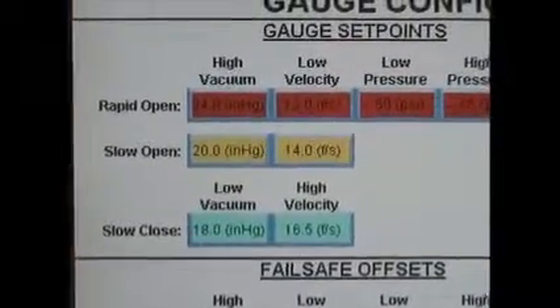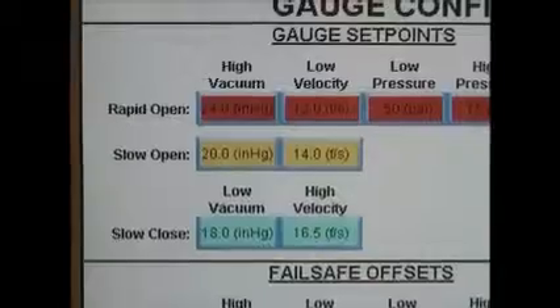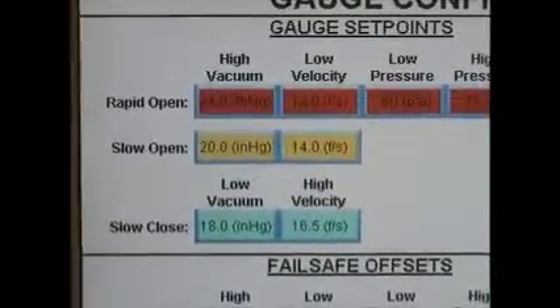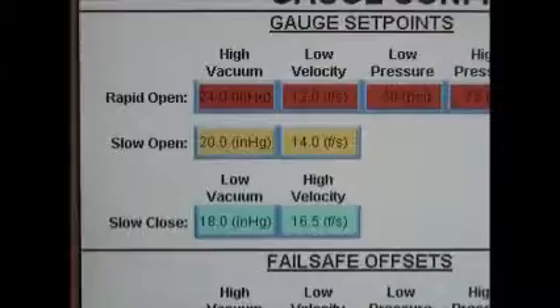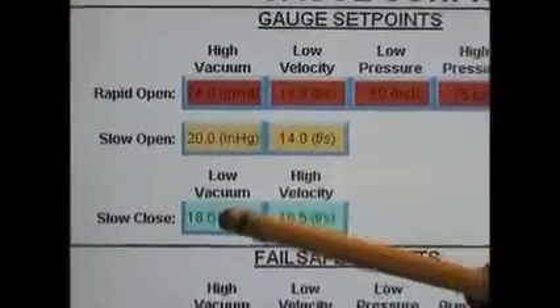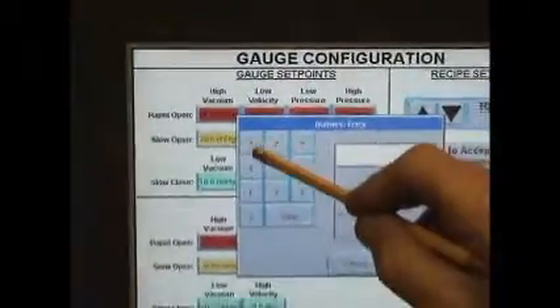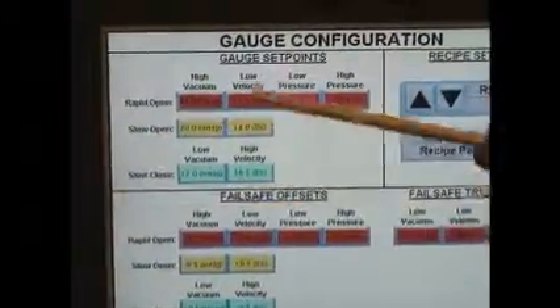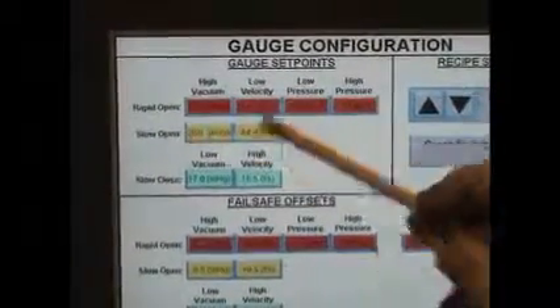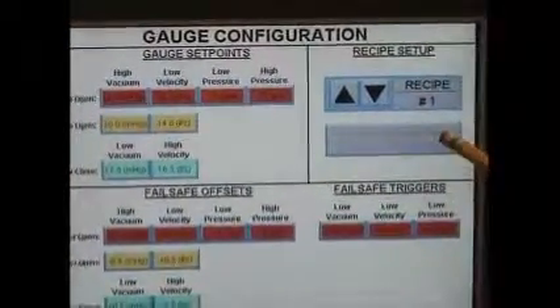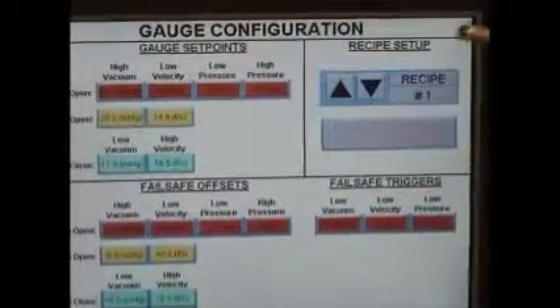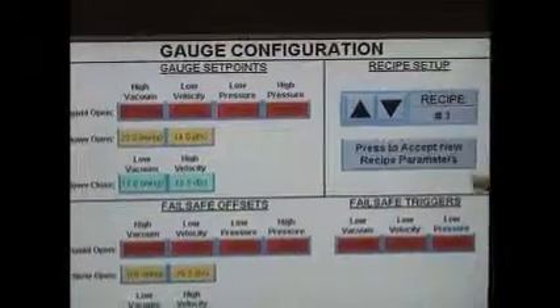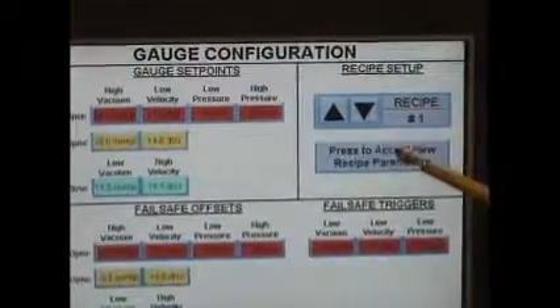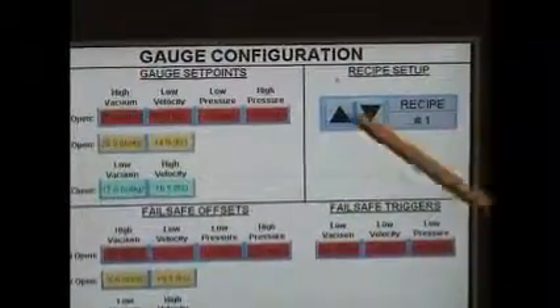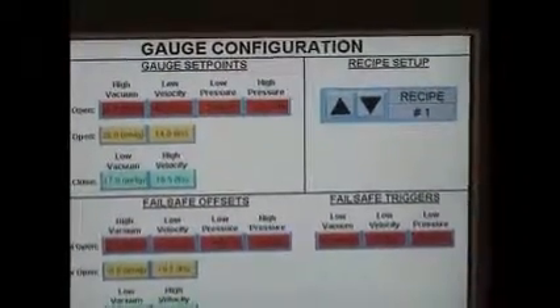or could be millimeters of mercury. Our slow close set point is where our turquoise and green zones come together. Currently we're set at 18 inches of mercury. Let's change that down to maybe 17. Simply touch and enter. Now we've made that change. Since we've made that change, we need to press accept new recipe parameters. We are currently running on recipe number 1, so to make the change we just did, we're going to touch that. Now that set those parameters to recipe number 1.